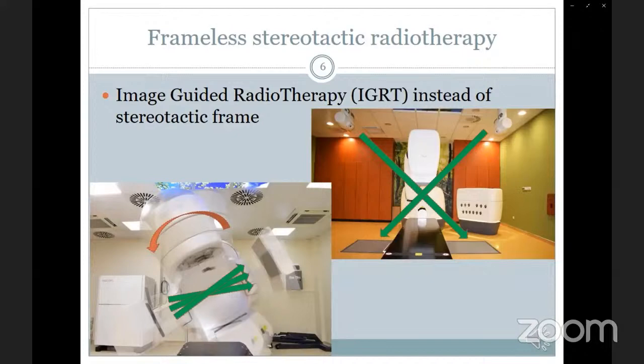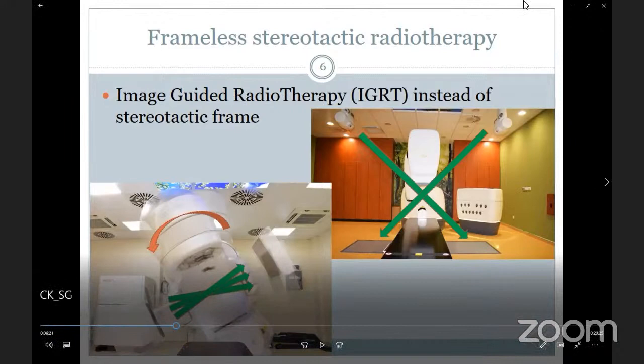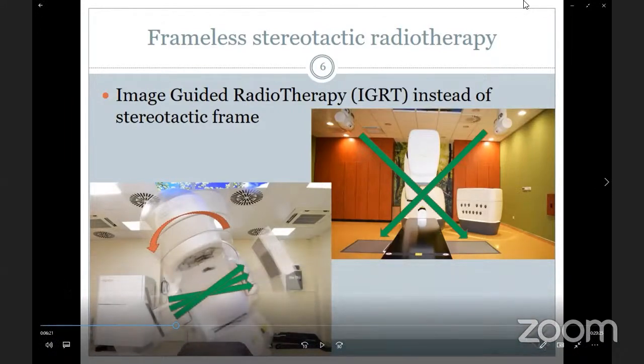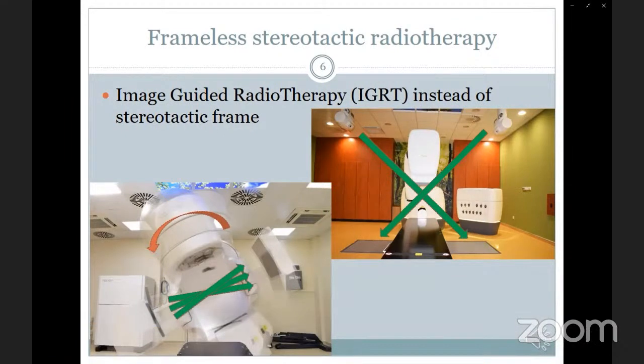For example, on the right side you can see the CyberKnife system, with 2 X-ray sources and 2 X-ray detectors, and orthogonal planar imaging with a 2D imaging method. On the left side you can see a modern TrueBeam linear accelerator, a conventional linear accelerator, and by rotating the gantry we can create a so-called cone beam CT. With this method, we can deliver stereotactic radiotherapy treatments.